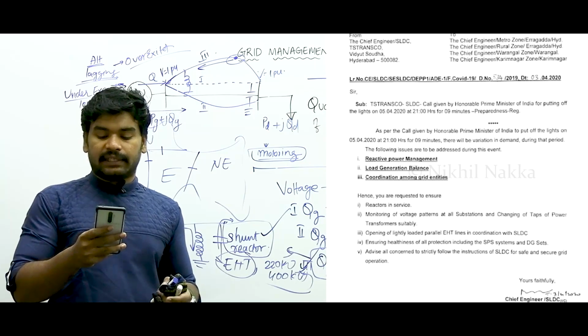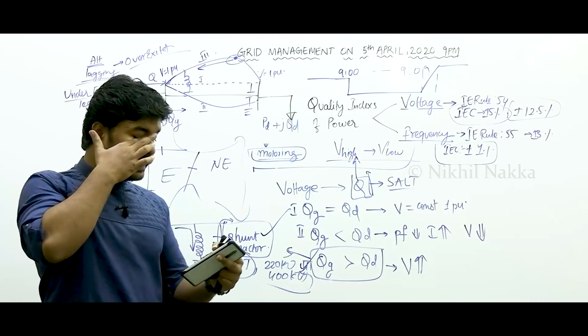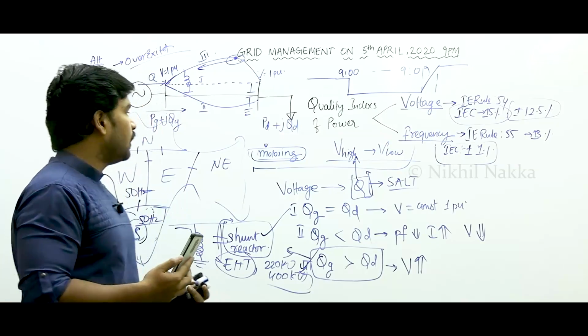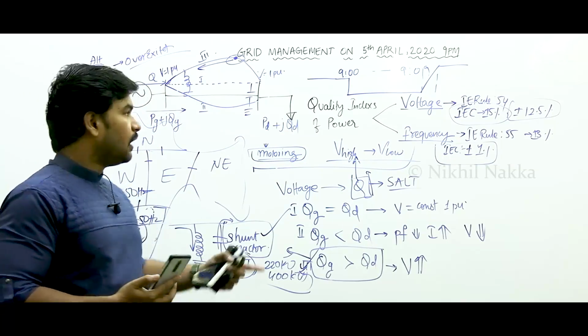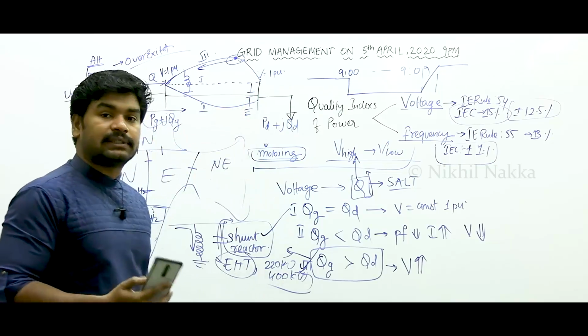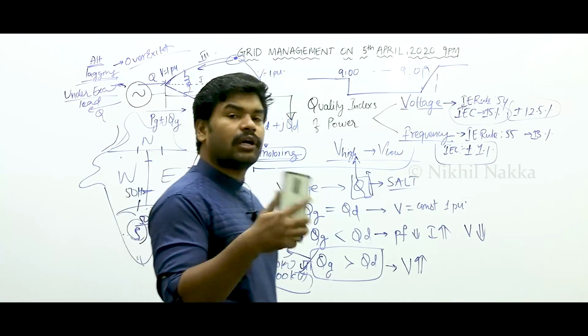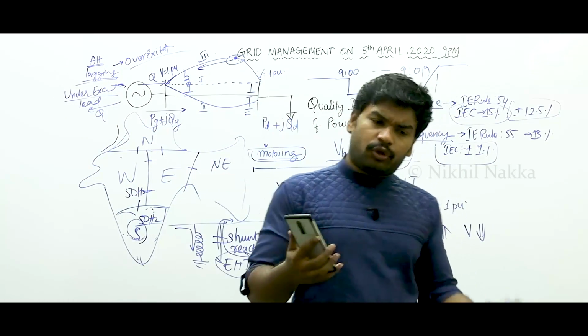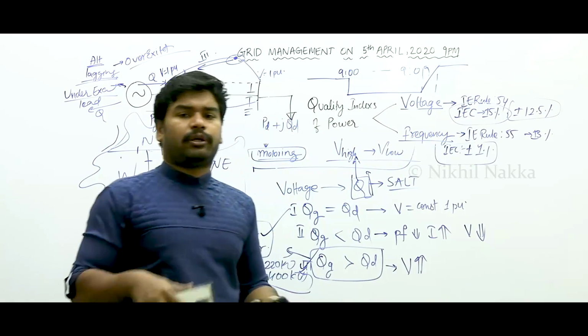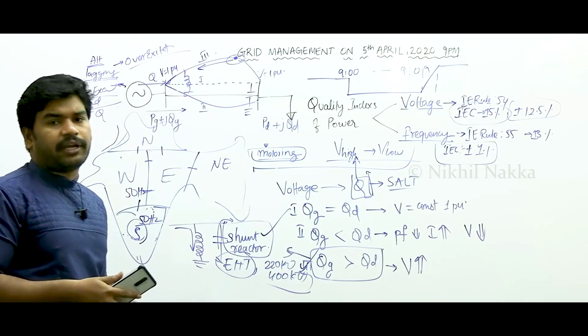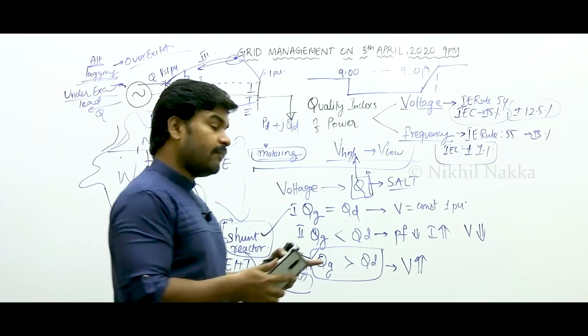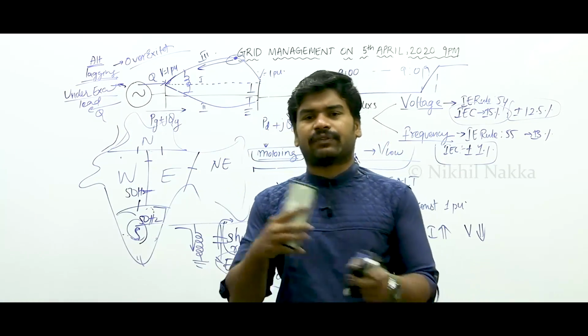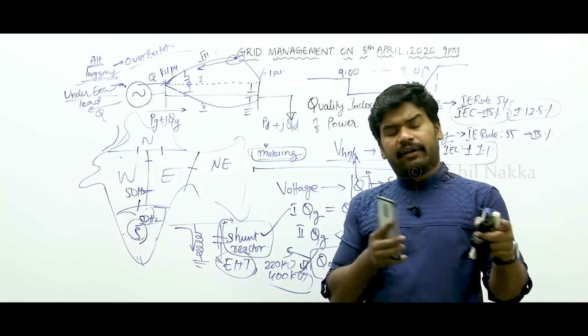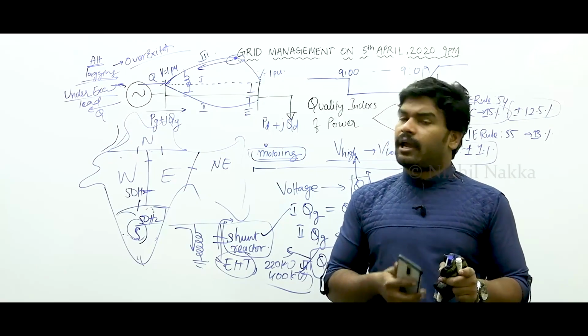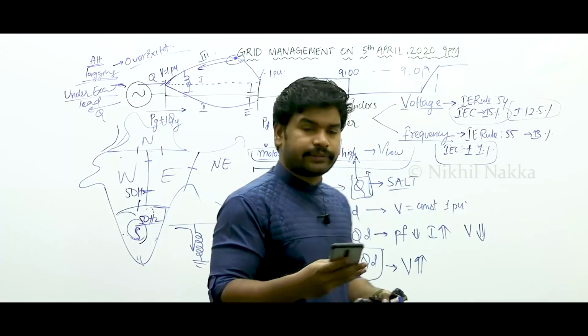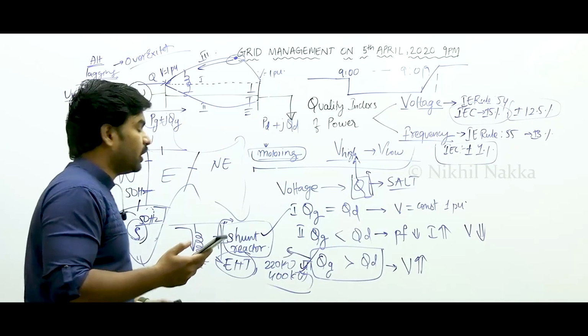So, see, why do you have to open these lightly loaded transmission lines? Because a lightly loaded transmission line, as I told you, has capacitance and is a source of reactive power, and it starts injecting a lot of reactive power into the system, and you are eating up the reactive power, and again reactive power is being generated. So this will again create a problem in managing the voltage. Therefore, whichever transmission lines are redundant, you can transfer the load into other transmission lines, parallel lines, and whichever is lightly loaded, you can immediately disconnect, in coordination with SLDC and all these things. That is what it says. I hope you got the point.